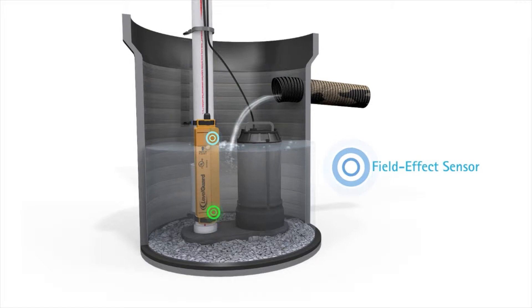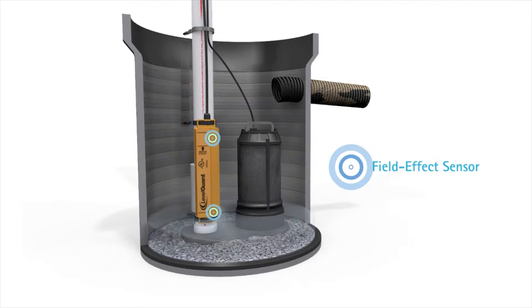Level Guard sewage and sump pump switches are designed with three field effect electronic sensors that monitor for the presence of fluids. Once upper and lower level sensors detect the presence of water, a solid state switch sends power to the pump via piggyback plug.